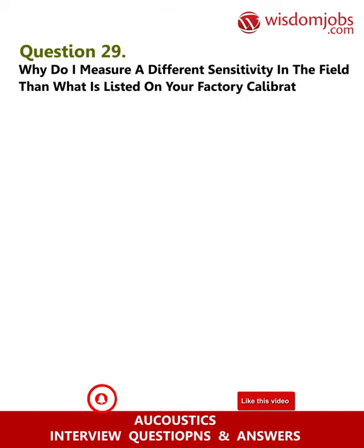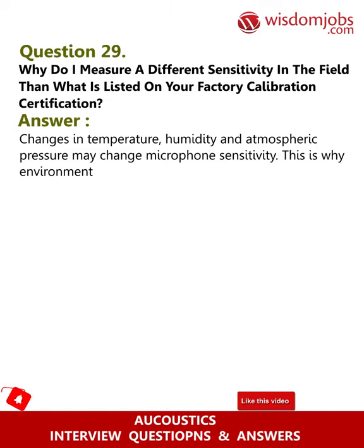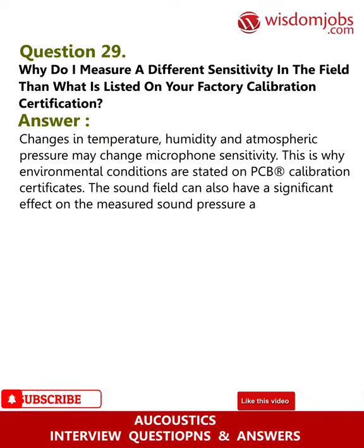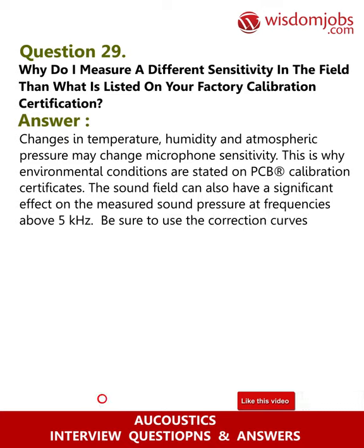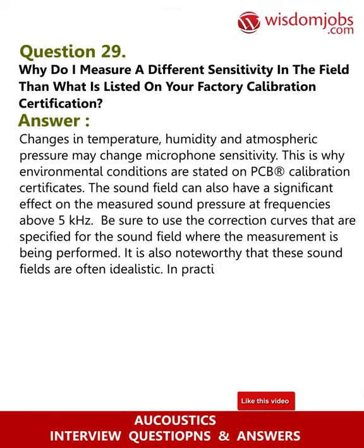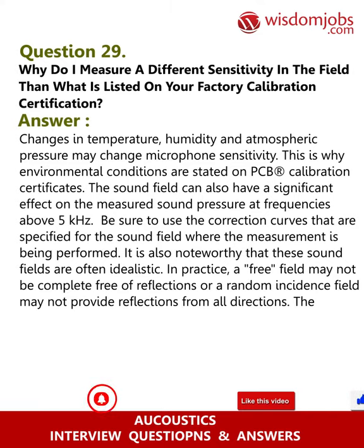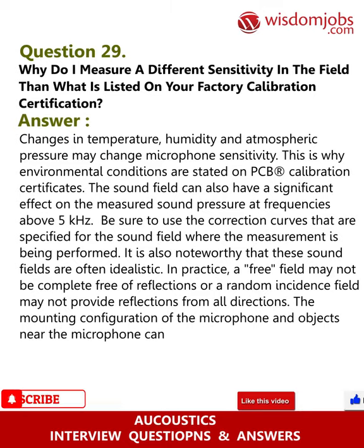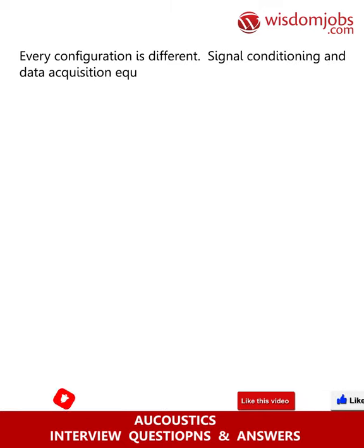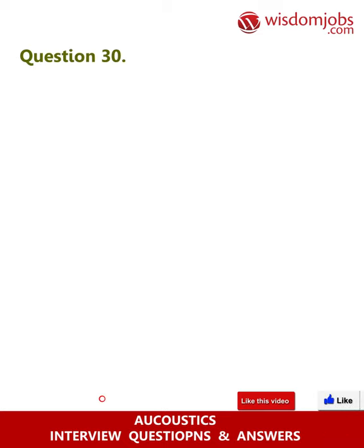Question 29: Why do I measure a different sensitivity in the field than what is listed on your factory calibration certification? Answer: Changes in temperature, humidity, and atmospheric pressure may change microphone sensitivity. This is why environmental conditions are stated on PCB calibration certificates. The sound field can also have a significant effect on the measured sound pressure at frequencies above 5 kilohertz. Be sure to use the correction curves specified for the sound field where the measurement is being performed. Free fields may not be completely free of reflections, and random incidence fields may not provide reflections from all directions. Mounting configuration, nearby objects, signal conditioning, and data acquisition equipment can all affect the measurement by limiting dynamic range or attenuating the signal at different frequencies.